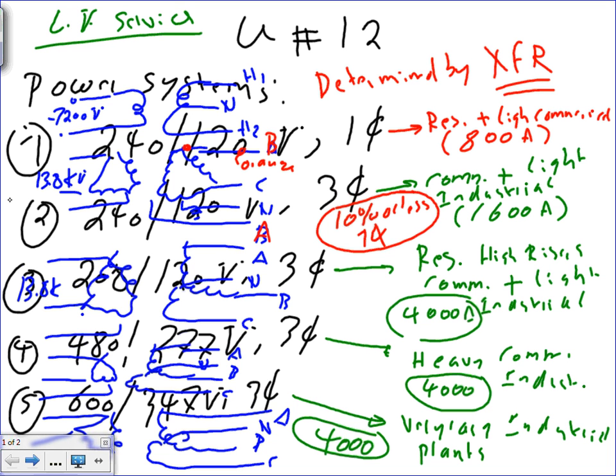You would never use this on a commercial building, this service. It's not a commercial building service. It's not an industrial building service. This is specifically rated for when the load is very small, the low voltage line to neutral load is 10% or less. Yes, sir. So delta is really dependent on the application being used. Absolutely. All the 3-phase I'm going to be talking about, guys, are application dependent. Delta, especially the delta center tap, guys.